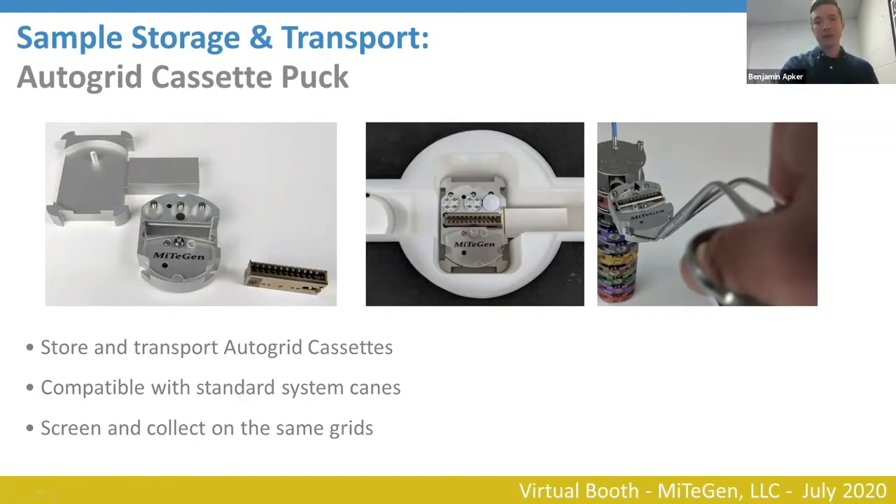Here's an image of it being inserted into a standard cryo cane that would use the CryoEM puck, but you could also send it in the transport cane — an accessory to the standard puck storage. This design goes inside of the standard cassette loading capsule or vessel, and you can transfer clipped grids from grid boxes into the cassette. The cassette can then be sealed using a protective lid and transferred using the same tongs you use to move the other pucks around.